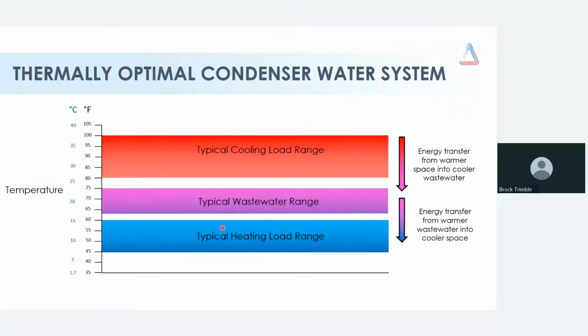Now, wastewater is an excellent source because it can be used not only for energy recovery, but also for energy rejection. So, in this, we're able to provide basically a source for heat sink and heat source when it comes to heating and cooling. If you look at this chart, you'll see wastewater is really in this nice range. It's a beautiful ambient temperature where cooling loads are able to reject energy into wastewater using it as a heat sink, or when you're looking at heating loads, you're able to take energy from that wastewater and send it into your building space to be used for heating source. So it really provides this excellent medium sort of energy availability to use for two different applications, heating and cooling, with this nice visual representation here.